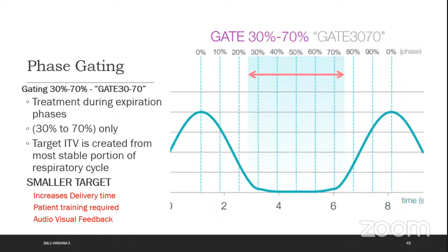As I said, there are two kinds of gating, which are phase gating and amplitude gating. Don't confuse it with phase binning and amplitude binning. The process is kind of similar. If we put the gate on the x-axis, in the 30% to 70% of the respiratory cycle, that is called phase gating. But if I say I can radiate when the patient breathes to 90% of his respiratory capacity, that is called amplitude gating. Amplitude gating is more possible if you use a technology like Active Breathing Coordinator with Elekta, because that uses a spirometer to look at the volume of breathing.